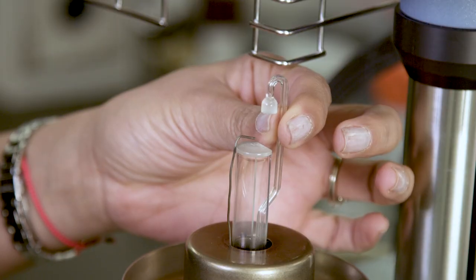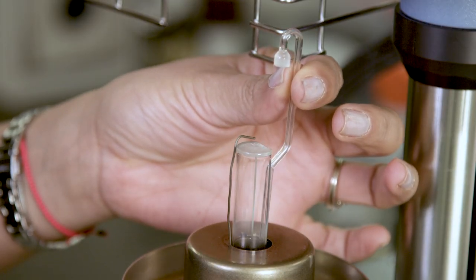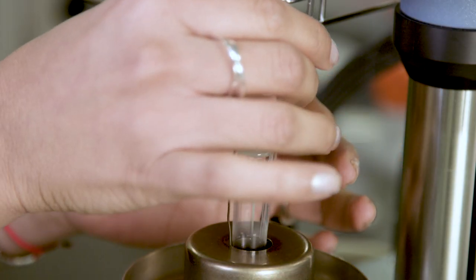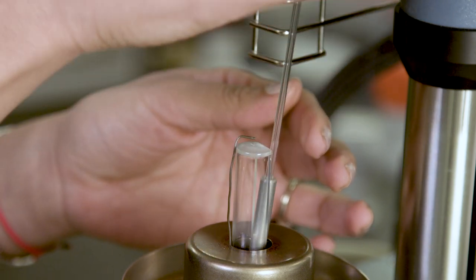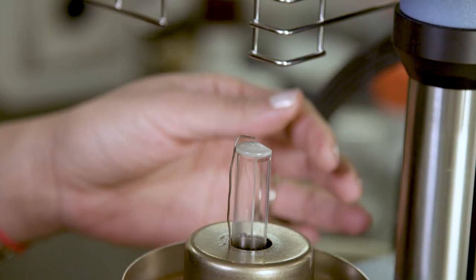Since the configuration of the Film Fiber Accessory is different from that of the other types of probes, you need to follow these steps to install the Film Fiber Probe and Stage. First, remove the installed probe. For a detailed explanation on how to remove the probe, please click on the link below.